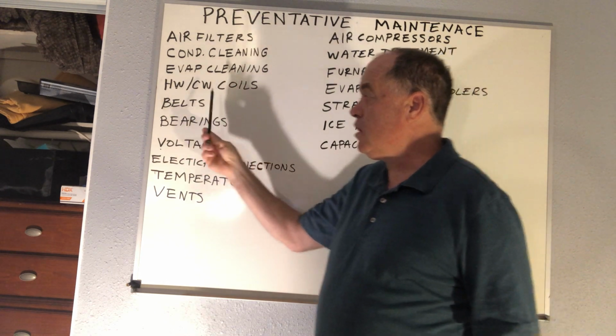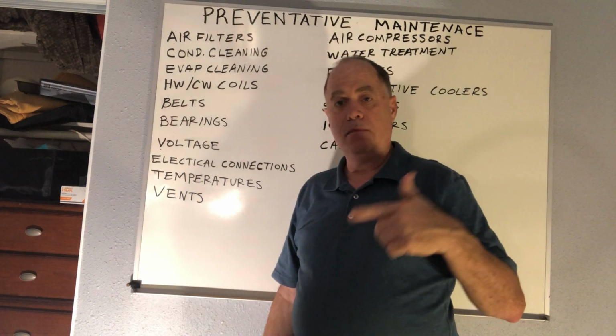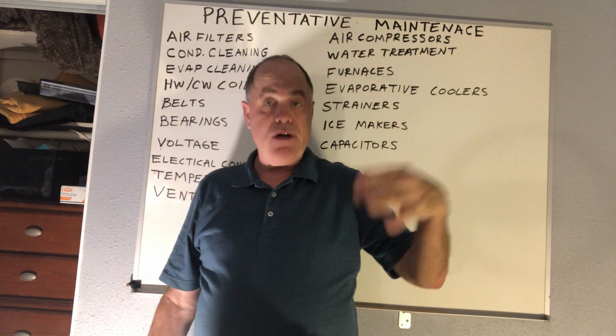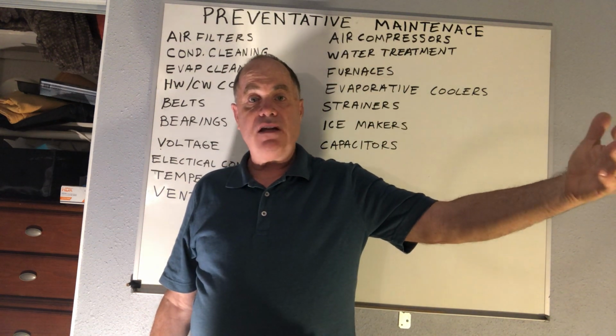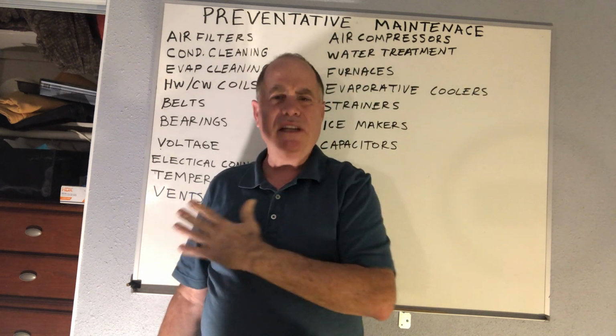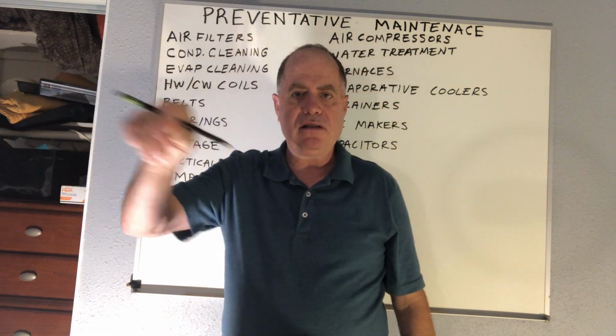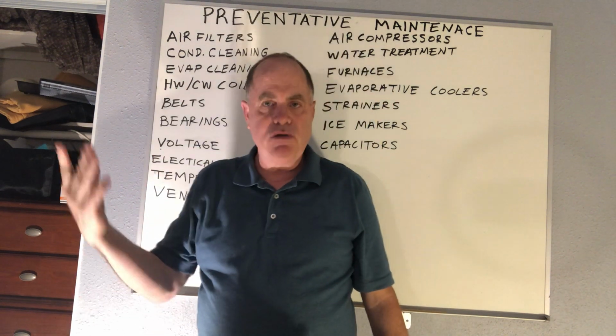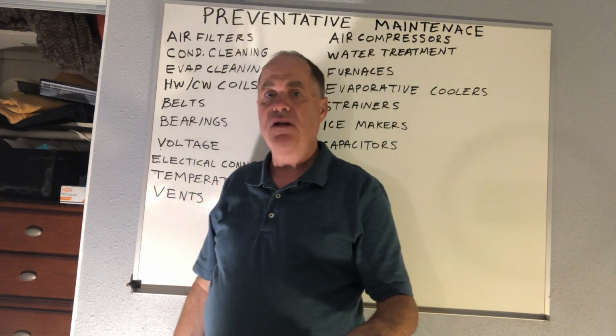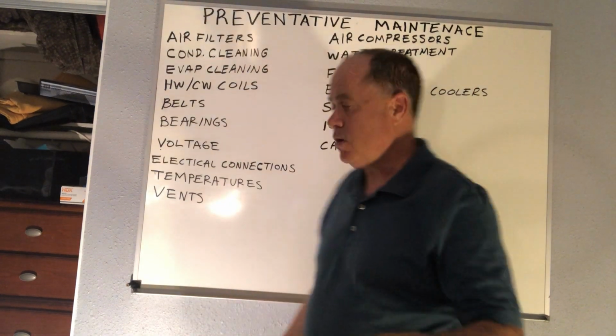Also, with this, cleaning condensate drains is a big part of maintenance, taking and blowing that out. Now, one of the things I even like to do, if you pressurize a system with nitrogen and then you're leak checking it because you're repairing, not doing maintenance, and then you have to release that dry nitrogen to the air, a lot of times I'll use that to blow out and clean little things, little condensers or drain lines. Using something like dry nitrogen even to purge out your condensate drain lines is important because they can over time get plugged up with gunk, okay?